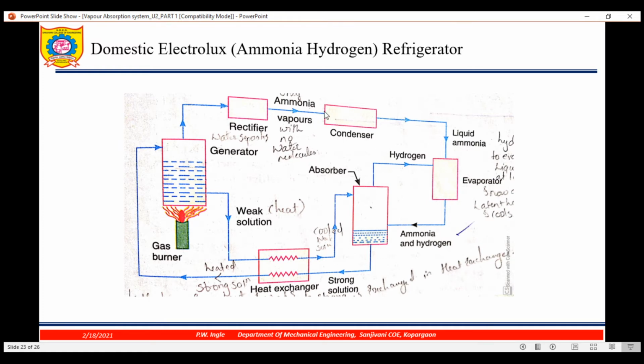Now here you see ammonia vapors, which are condensed in the condenser by condensation, will be converted to liquid ammonia, and this liquid ammonia goes to the evaporator. In the evaporator, hydrogen is used to increase the rate of evaporation. Now the mixed ammonia and hydrogen goes to the absorber, and here pressure reduces. Water has the ability to absorb ammonia. Hydrogen will not be absorbed. Hydrogen circulation is limited to this circuit only.